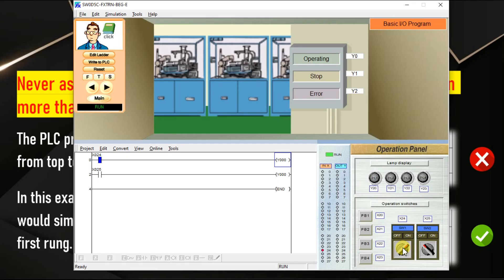What happens? My output Y0 is in off state, but input X24 is on state. As discussed previously, the output Y0 must be turned on. Why is it not turning on? Because we used double assignments of same output with different inputs and different input statuses.